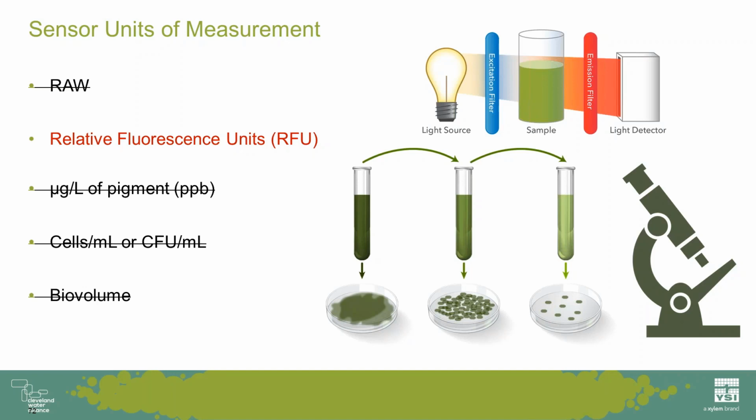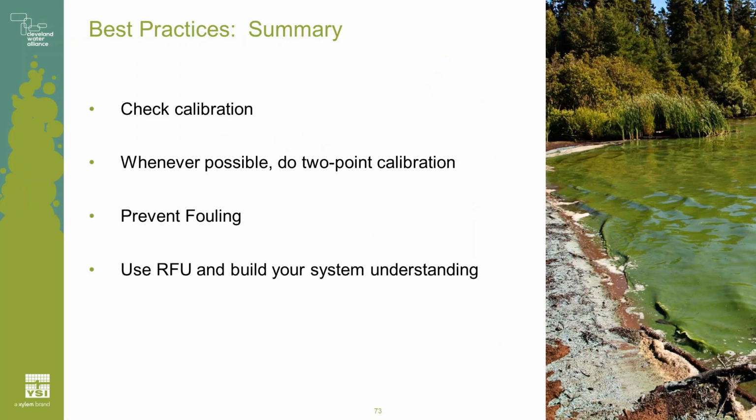Use the monitoring data to help you decide if or when you want to collect samples. So wrapping up this final section, you need to check your calibration frequently, and whenever possible, do a 2-point calibration, take measures to prevent biofouling, and please use RFUs.